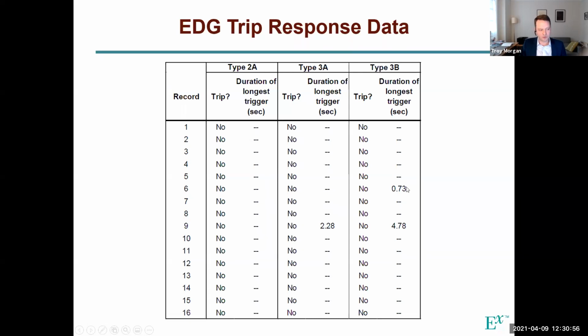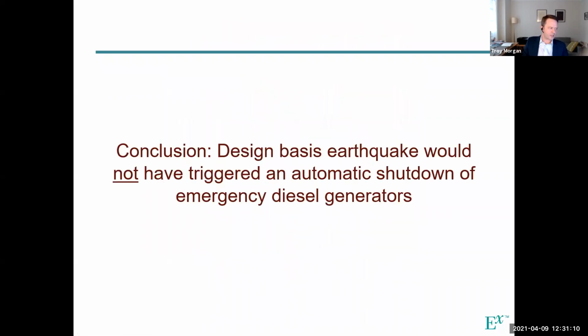What we found was that there were only 3 instances, or realizations, of design basis shaking where we got a trigger, and in no cases did that trigger signal exceed the 5-second threshold. So we were able to conclude that design basis earthquake shaking would not have triggered a shutdown of the generators.